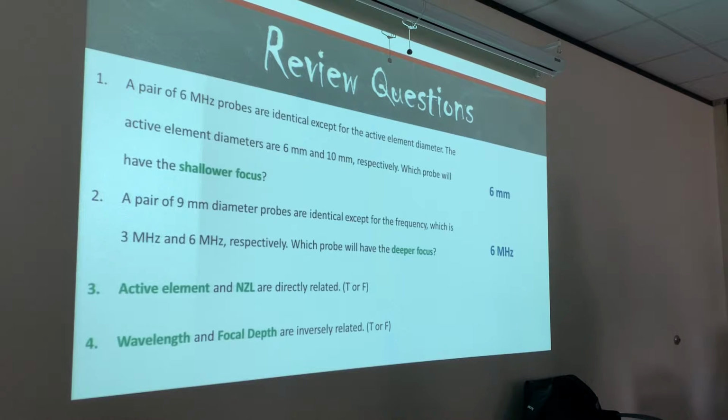So our active element and our near zone length. If I have a bigger active element, what's going to happen to the depth of my focus? It's going to be longer, right? So my near zone length is also going to be longer. So of course, the size of our active element and our near zone length are going to be directly related, guys. That's a true statement.